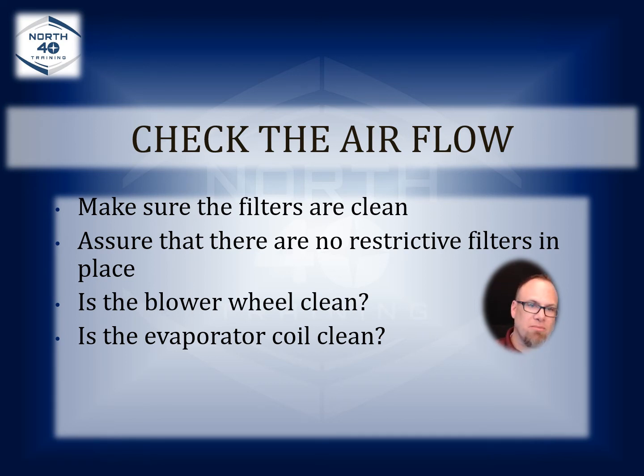You know, that's what the manufacturer gets the efficiency ratings with. That's what gives you the best airflow, but that also, on the opposite side, is the least effective on the filtering side of things. But you can't take that into consideration because these furnaces were never meant to filter the air. They're meant to move the air so that we can create a comfort level through our heating and cooling system that's sufficient for the customers and efficient for the home.